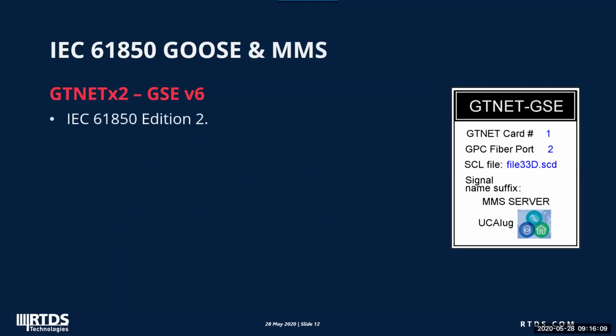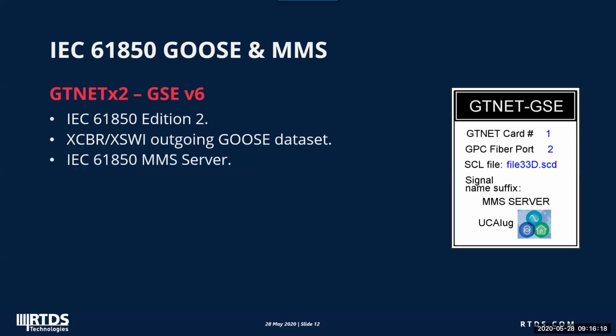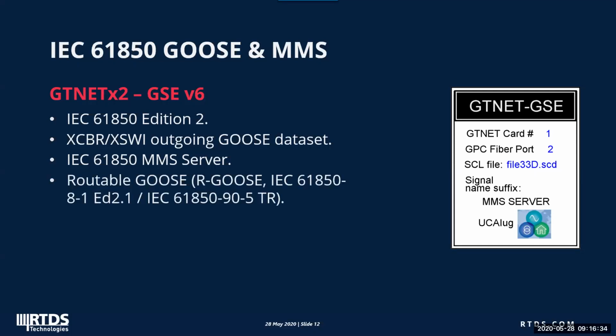V6 component supports edition 2 of the standard. And besides GGIO, V6 supports logic node XCBR and XSWI for outgoing Goose dataset. Starting from version 6, IEC 61850 server with limited functions is supported using the GTNet X2's IP address. Another new feature is the routable Goose. Now, due to the limited time, these 2 new features will be the focus of today's demo.